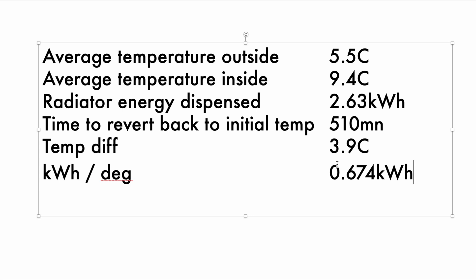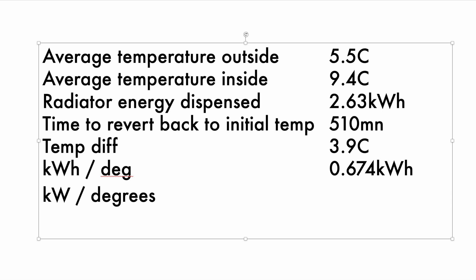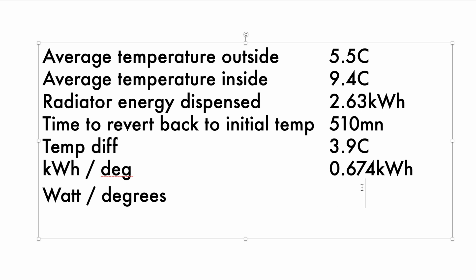Now, very importantly, we want to know the loss in terms of actual power — what would be the stable radiator power that would compensate for the losses? That's 0.674 kilowatt hours divided by 510 minutes expressed in hours, giving us kilowatt hours per hour. We're expressing this in watts rather than kilowatts.